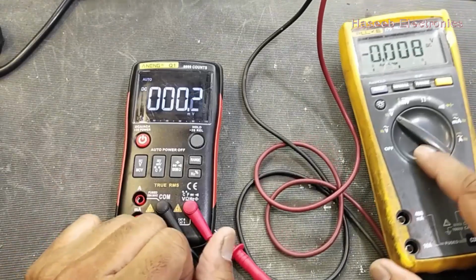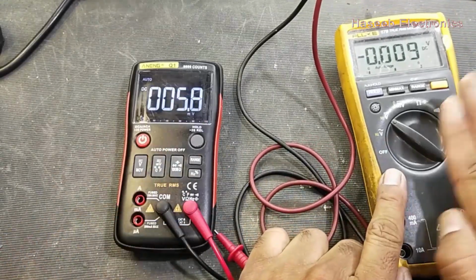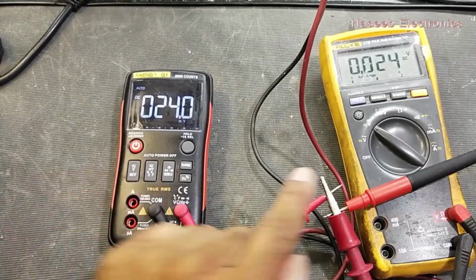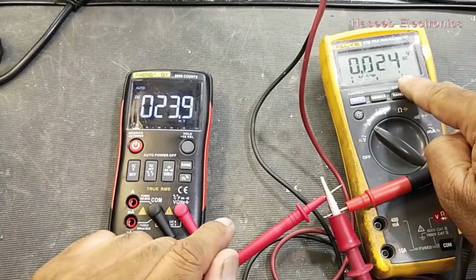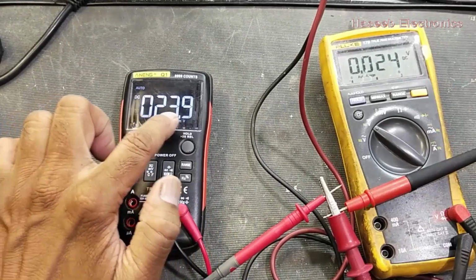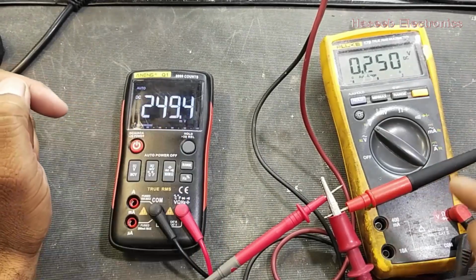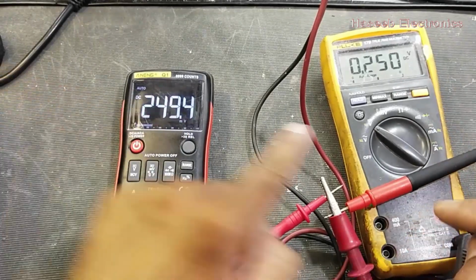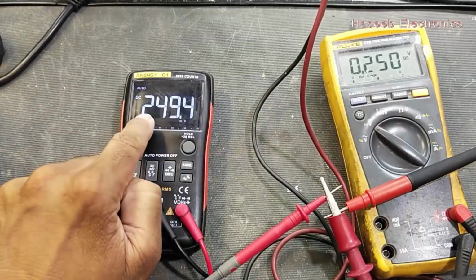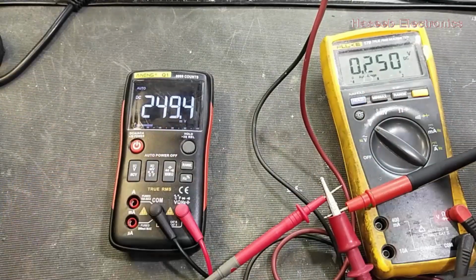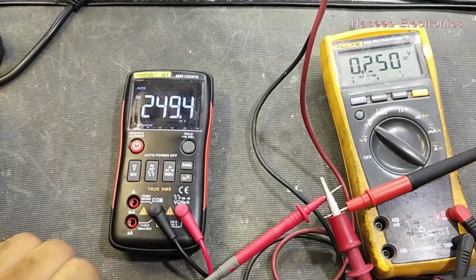We will compare this multimeter with Fluke. It is not a standard, but we can compare. I applied 24 millivolt signal. Here we have 24. Here is 23.9. I applied 250 millivolts. 250, 249.4. So it is acceptable.